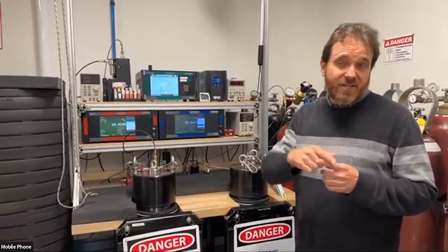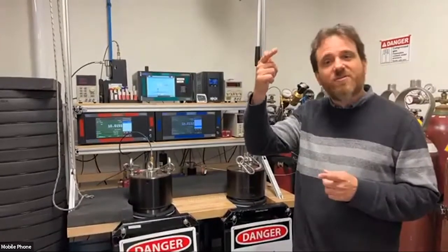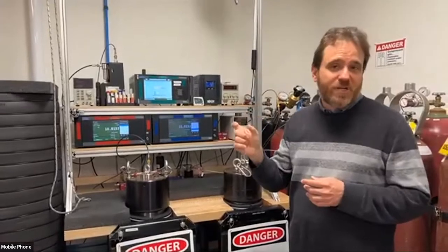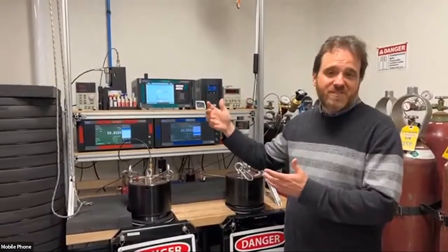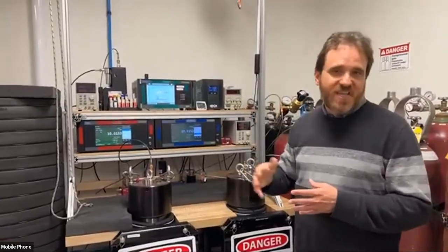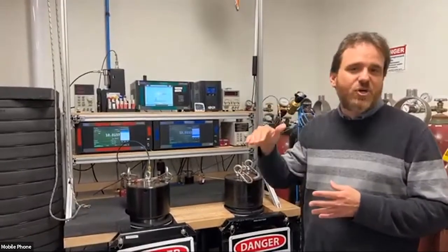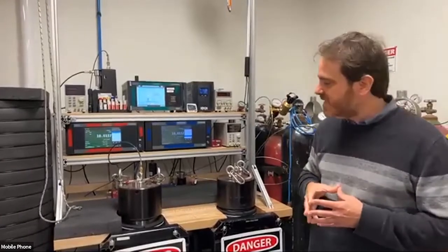In order to confirm hysteresis, we do an increase in pressure, and we also depressurize. The actual calibration points, I should say the measurements taken between our reference standard as well as the DUT, are taken during the depressurization cycle. That's when we plateau, stabilize, and take our readings for the 10 different points.